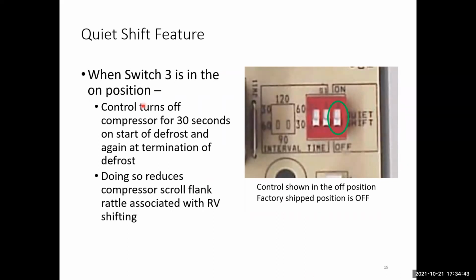Okay, the quiet shift: when switch 3 is in the on position, the control turns off the compressor for 30 seconds after the defrost, and on defrost on the thermostat, again at termination. So as soon as the compressor turns off for 30 seconds, it switches over, hits your reversing valve into the cooling mode. 1 to 2 seconds after that, the compressor starts back up. It does that at initiation and at termination to reduce the compressor scroll flank rattling associated with the reversing valve shift.